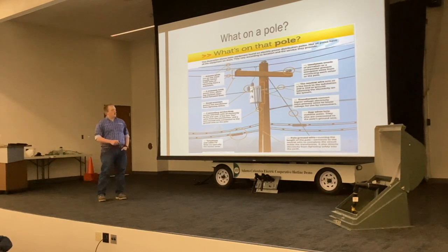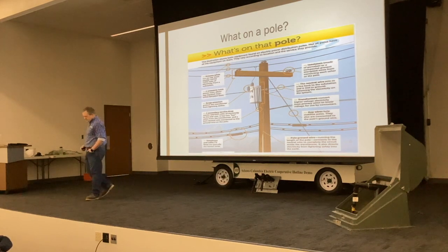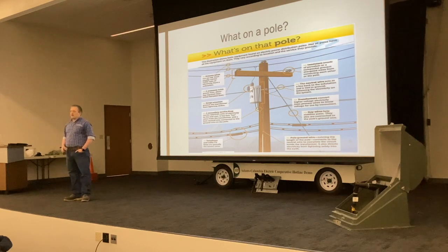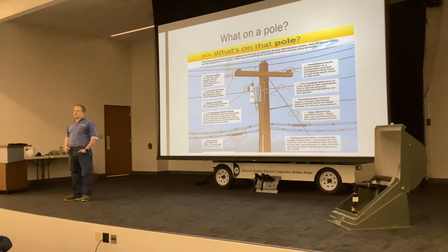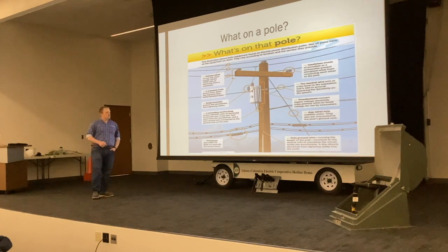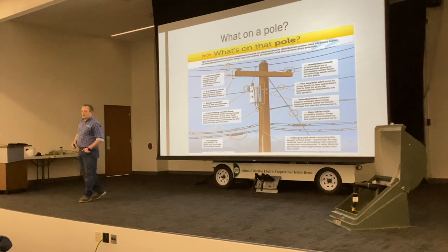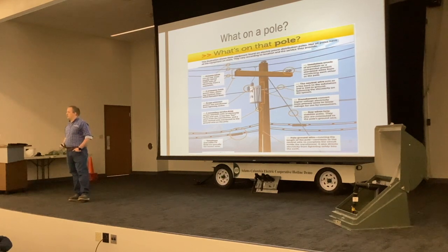From there, we want to talk about this guy wire that comes down at an angle. Our guy wire is high tensile strength steel. It has absolutely no give, no stretch in that. And we get it fiddle string tight. And that is used anytime we need to put an angle on the pole, because roads aren't all built completely straight, right? You guys do a great job, but whoever designed it put some extra curves in there, right? So we're going to follow those roads most often.